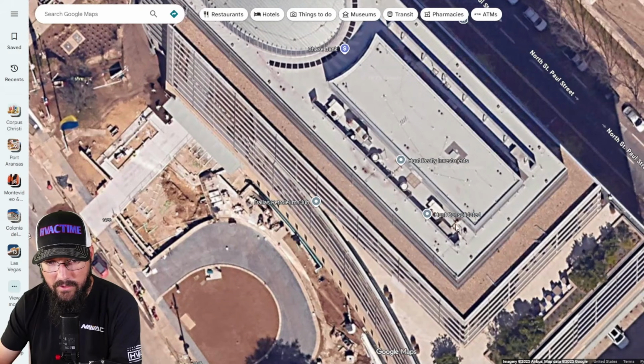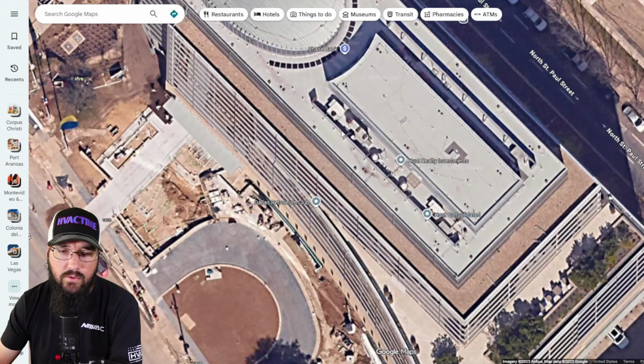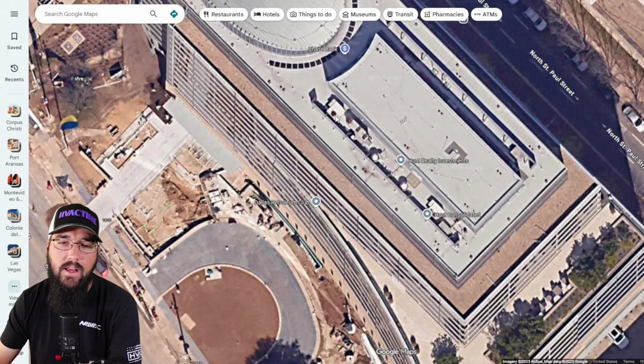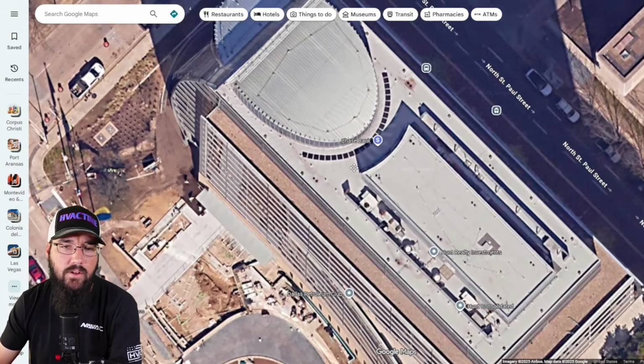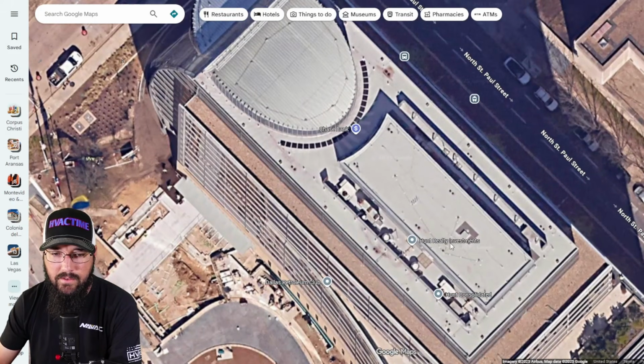Now we've got this thing in the way, but it looks like that might be another tower back over here. RTUs and chillers don't have a fan deck that looks like this. The only thing with fan decks like this, where everything's offset, are cooling towers. I've never seen a large scale RTU with a single condenser fan, it's just not a design I'm familiar with. What that tells me on this particular building is this is a water-cooled system, so they've probably got water-cooled equipment, could be centrifugals, could be water-cooled screws.